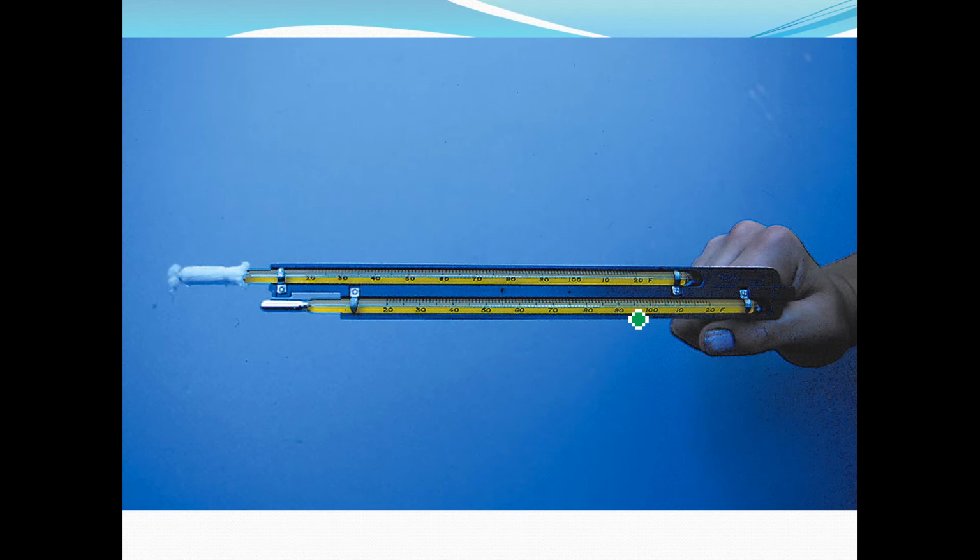On the other hand, if the humidity of the air is really dry, it's really low, that means that moisture will easily evaporate off that wick. That means a lot of moisture is going to evaporate, more latent heat is going to be absorbed by the water, that's going to cool the atmosphere even more. This temperature will be much lower. And in this case, the wet bulb temperature will be much lower than the dry bulb temperature. When that happens, when the difference between the two is really large, that represents a really dry atmosphere.